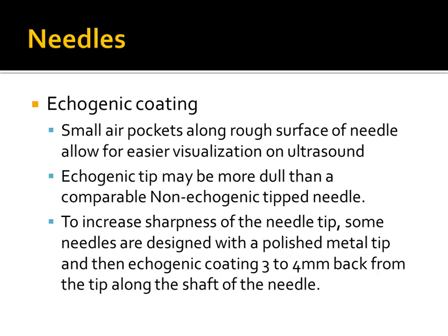Echogenic coatings on needles use rough surfaces that capture small pockets of air to allow easier visualization on ultrasound. However, if the echogenic coating goes all the way to the tip, the sharpness of the tip is not as great as a non-echogenic tip. For that reason, some people prefer non-echogenic needles entirely. Manufacturers also produce needles with partially echogenic tips — the very front end is not coated to preserve sharpness, while two to three millimeters back along the shaft there's echogenic coating. These hybrid needles have a partially echogenic coating to balance visibility and sharpness.